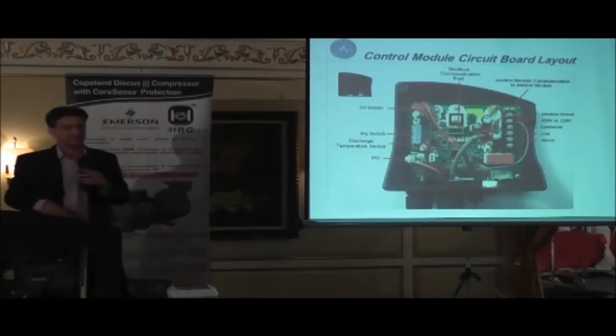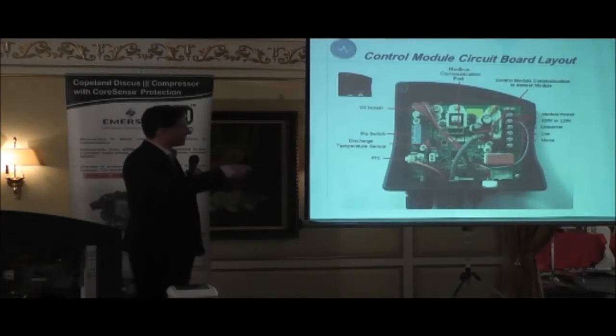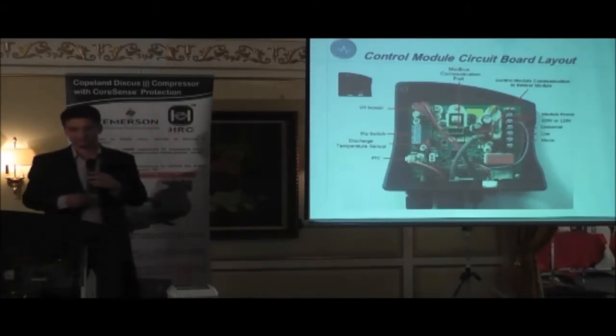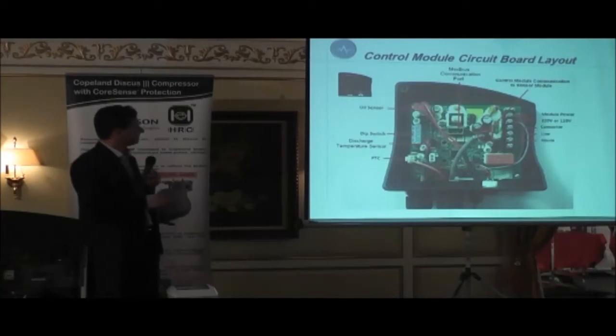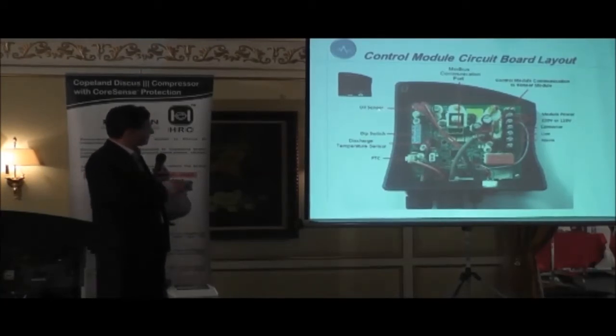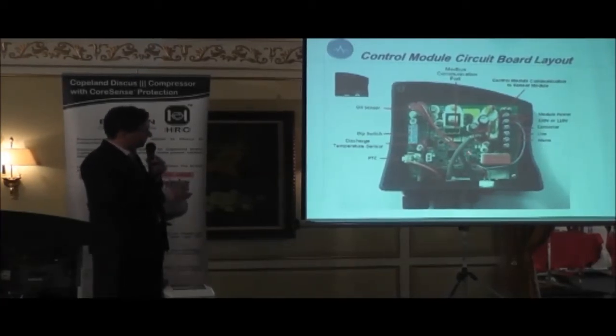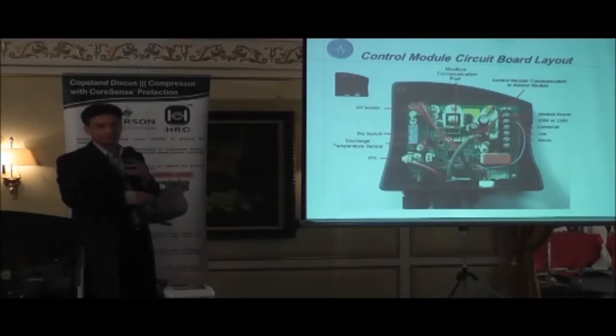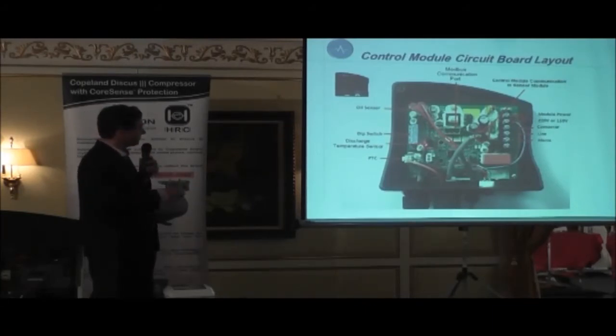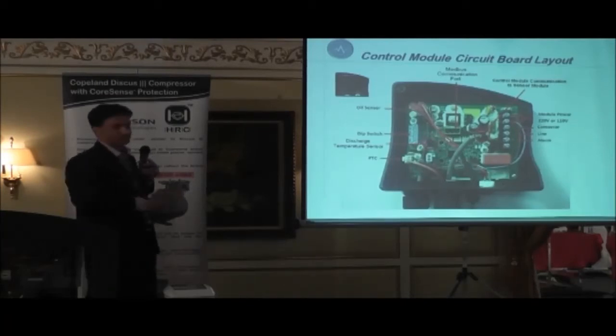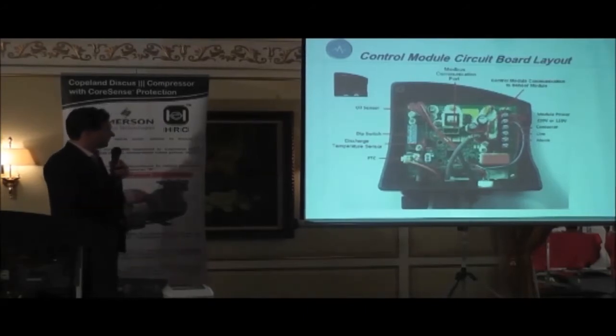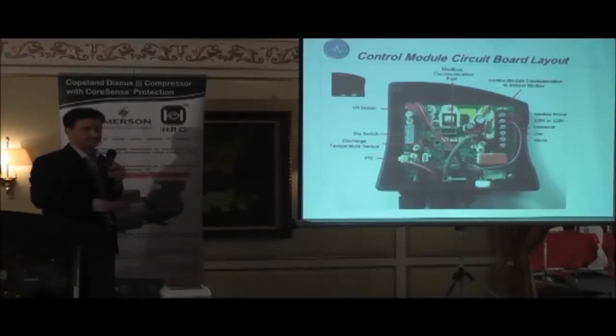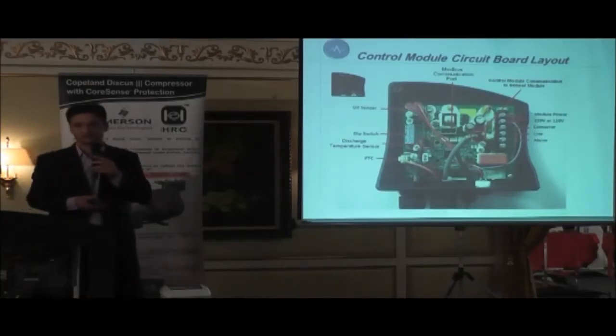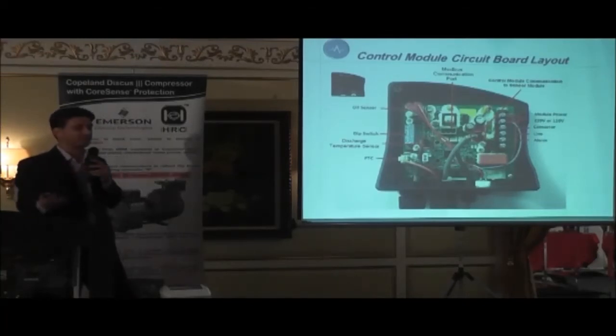We go now a little bit deeper. This is the diagnostic module. We've removed the front cover. These two wires are the oil sensor. Okay. This cable here is the discharge temperature sensor. The 4-pin plug here is the PTCs that are connected to your motor. So that would be equivalent to the PTCs that we had on the INT69.